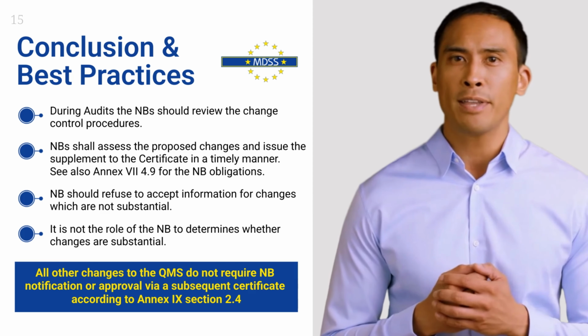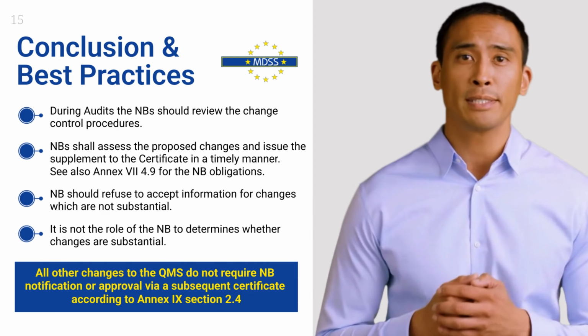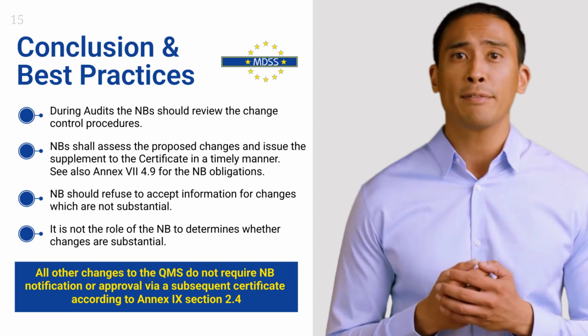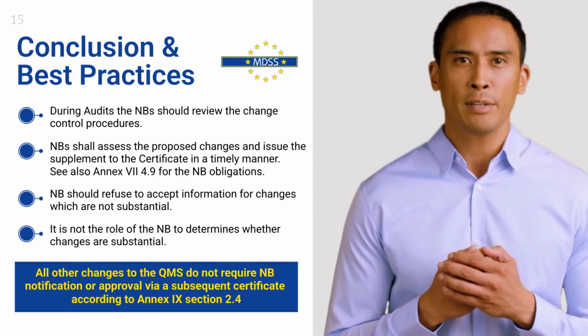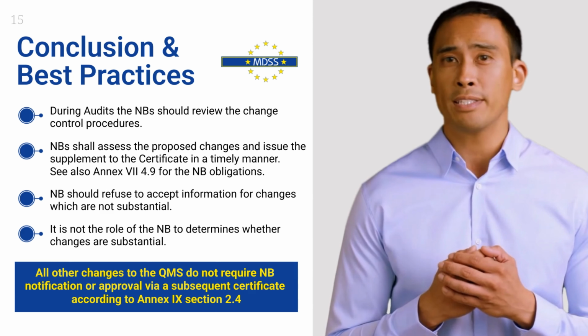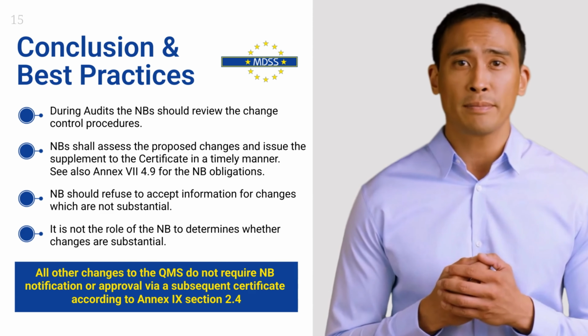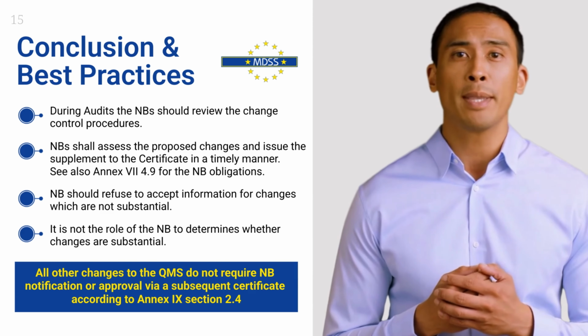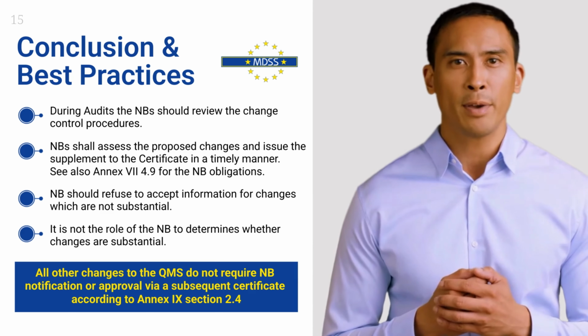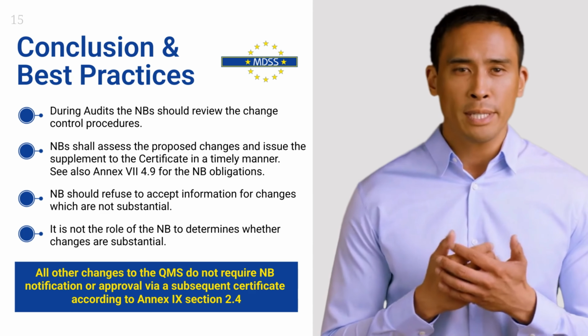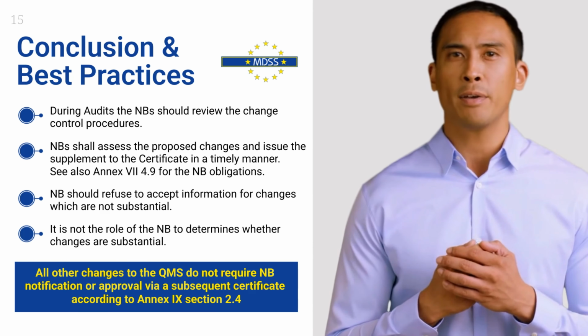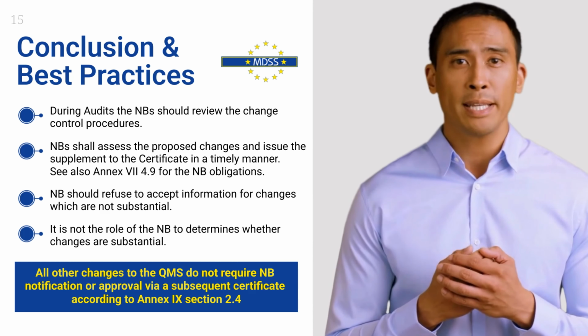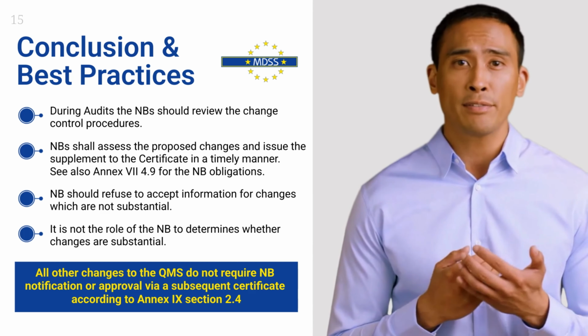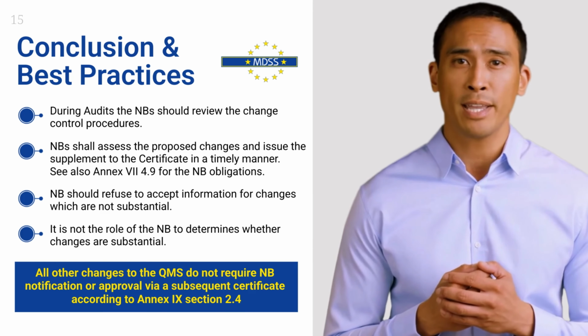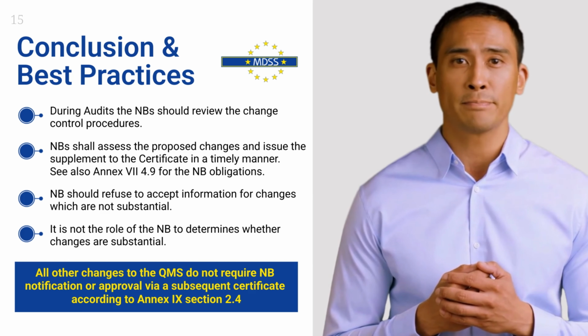Critically, the notified body should only review substantial changes as notified by the manufacturer. Refuse to accept routine or irrelevant change notifications that are not substantial. This reinforces the principle that only meaningful changes to the certificate require a supplement. By focusing audits on this decision-making capability, the notified body helps maintain a system that is both efficient and compliant, without unnecessary oversight or administrative burden.